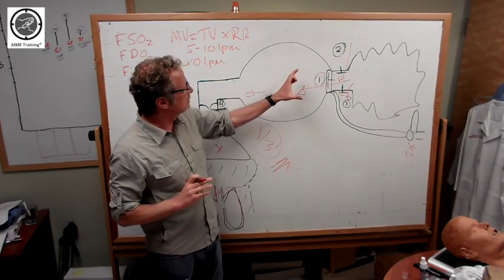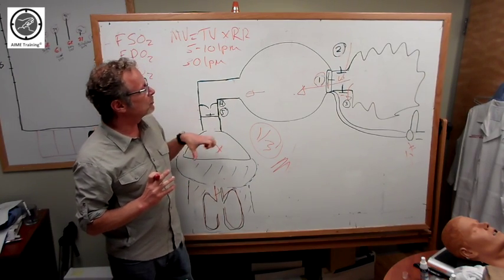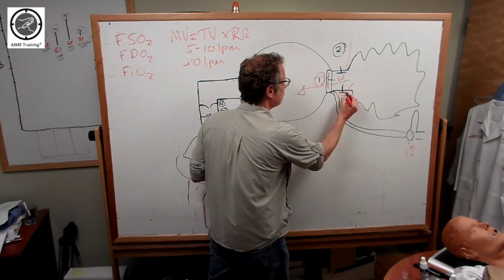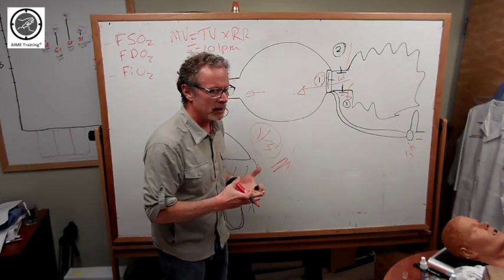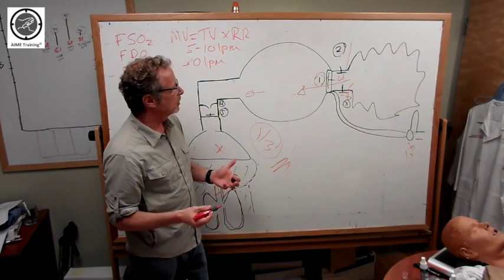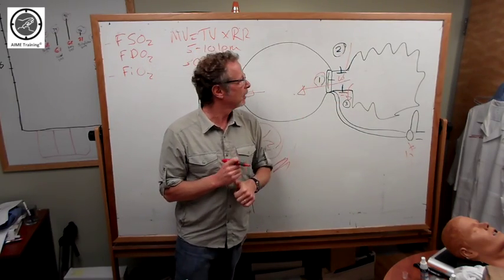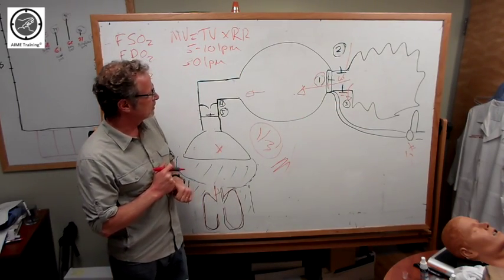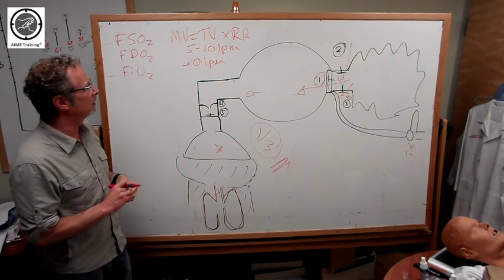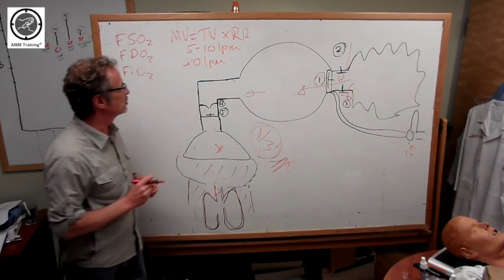The problem is that these two valves, even though they're meant for safety, can affect the amount of oxygen that you deliver to that patient through entrainment. Interestingly, as I said, this one's on the bottom and it's a simple disc valve, so it's susceptible to gravity, and this valve can sort of fall off of that reservoir and actually you can lose more of your oxygen and potentially entrain room air through that valve that's flopped down. There are also intrinsic leaks that aren't necessarily intentional within the system that will affect the delivery of flow and make this a third of what you expect.